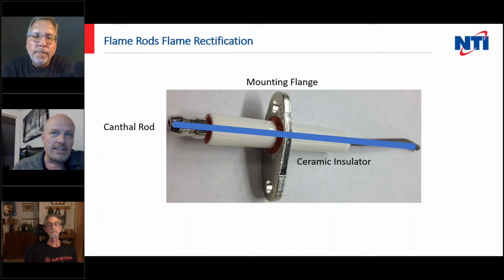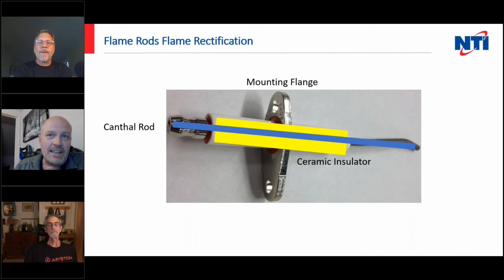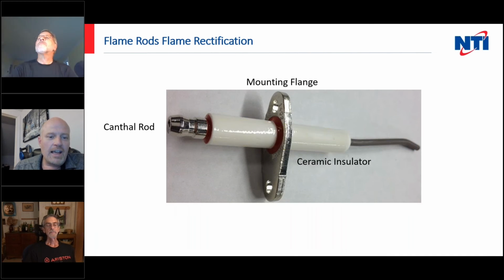The purpose of the rod is to conduct electricity. The purpose of the ceramic insulator is to isolate the rod from anything that it might touch that could be electrically conductive. So look for cracks in that ceramic. If there are cracks in it, it will give you lots of problems.